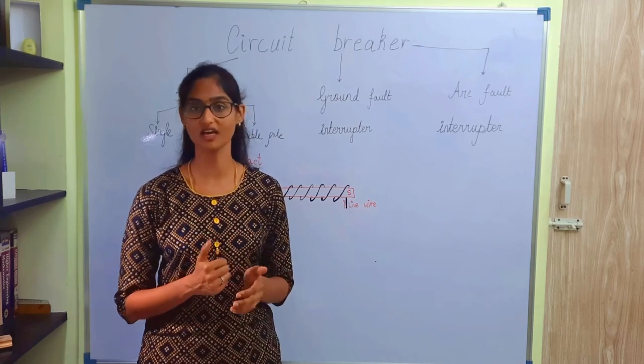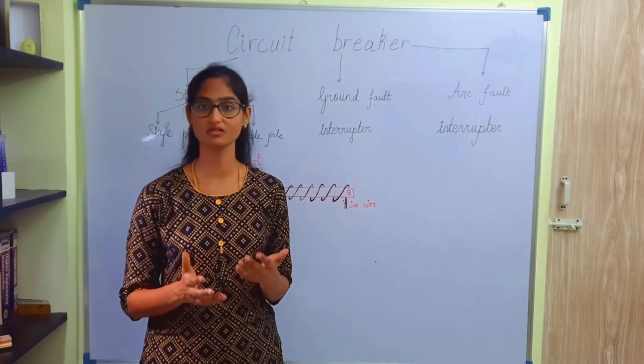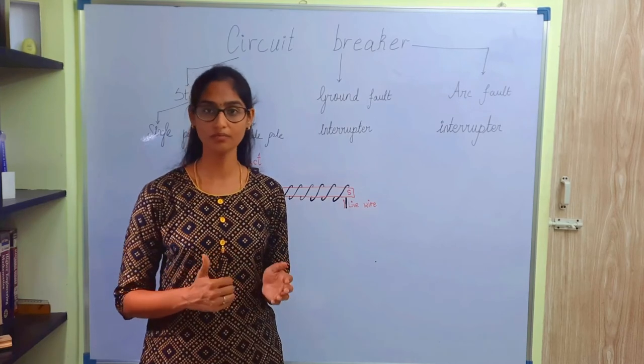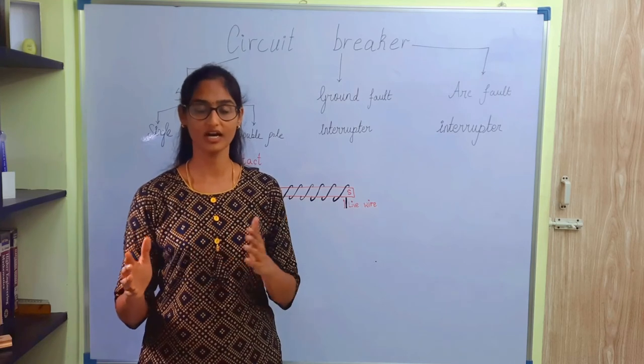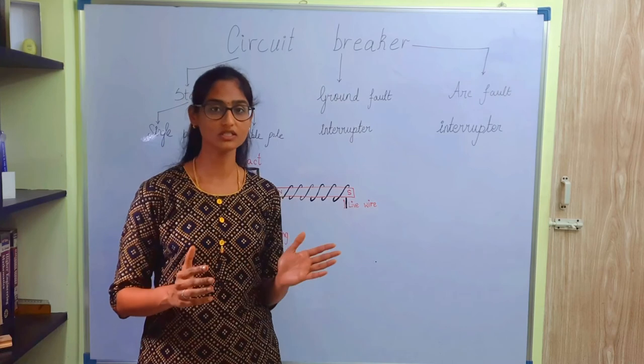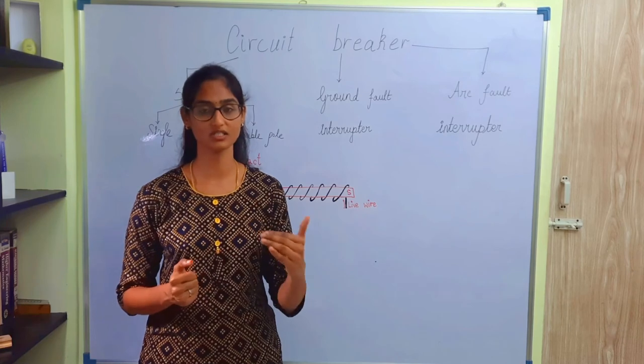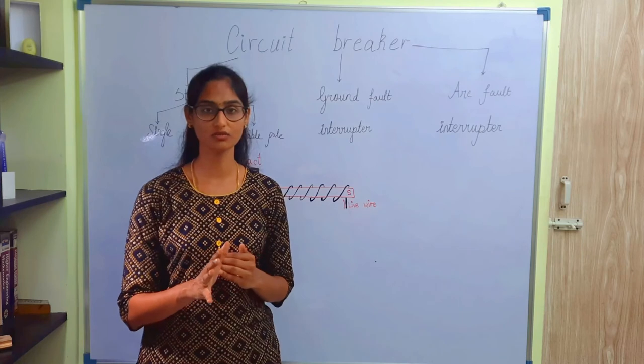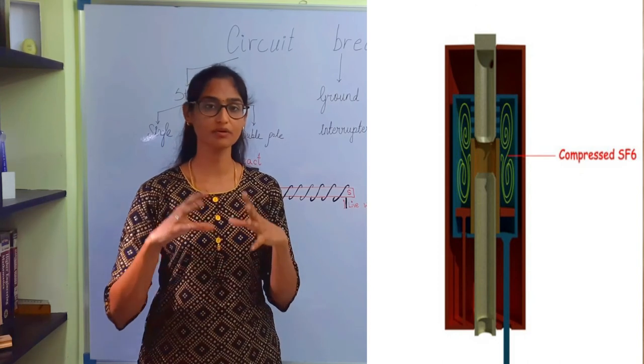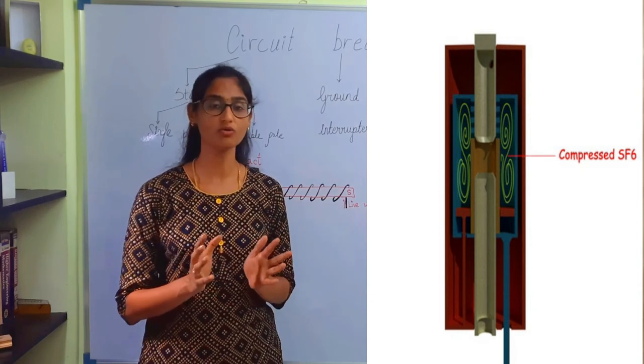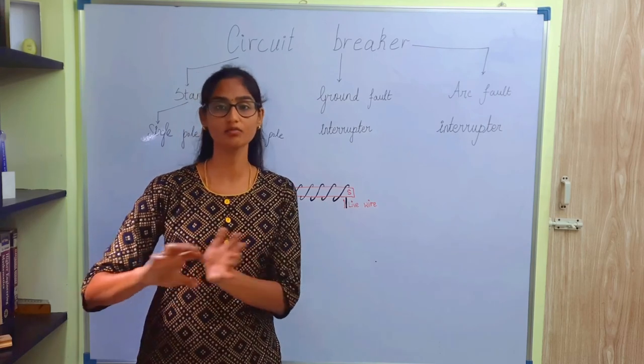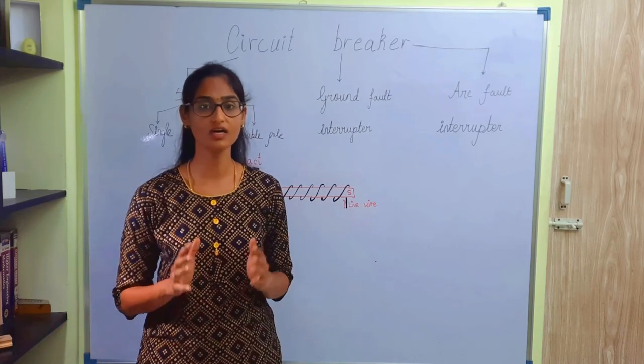We have this because SF6 is a very costly element. In India, it will be around 1000-1100 rupees per kg of it. So this is very costly. With every operation, we can't be spending for SF6 again and again. So what people do? They have a low pressure reservoir in the other end of the tube. They will be connecting the high pressure gas which flows into the chamber into this low pressure reservoir. So once this gas is entering the low pressure reservoir, it will be collected inside for the next operation. After this happens, it will be pumped to the high pressure reservoir where the piston moves forcefully thereby reducing the volume of the cylinder. When the volume of the cylinder reduces, the pressure builds up inside that gas chamber. So when the gas is sent into the arcing chamber, the gas will be sent in a very high pressure. Thereby it can absorb more ions and then it will move into a low pressure reservoir. This is how SF6 circuit breaker works.